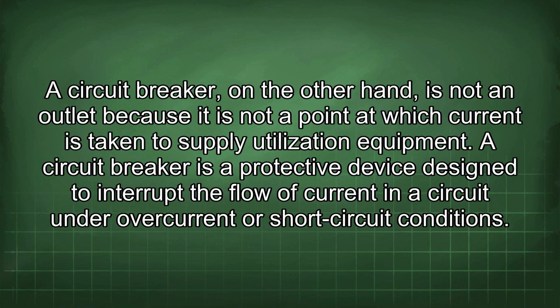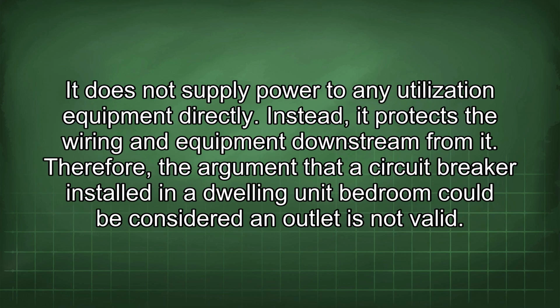A circuit breaker, on the other hand, is not an outlet because it is not a point at which current is taken to supply utilization equipment. A circuit breaker is a protective device designed to interrupt the flow of current in a circuit under overcurrent or short circuit conditions. It does not supply power to any utilization equipment directly. Instead, it protects the wiring and equipment downstream from it.